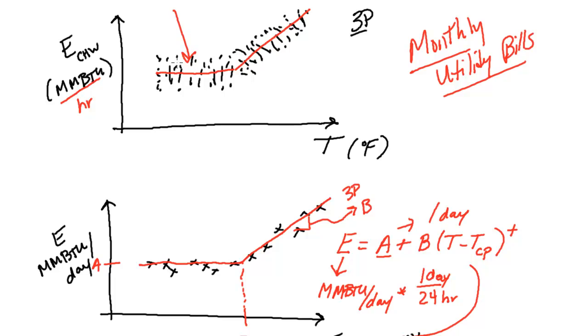Really the idea is to say, we're trying to get something that predicts all of this data, but let's just say you only took a snapshot in the springtime, and you only got this chunk. You came in for two weeks, and the temperature in that short period of time only ranged plus or minus 10 degrees F, in which you didn't get this whole range of temperature. You didn't see how your building operated under these different conditions.